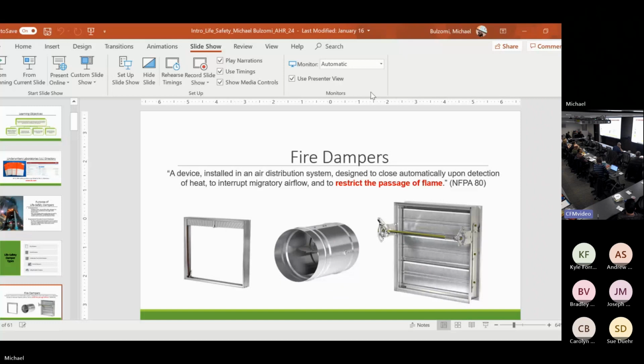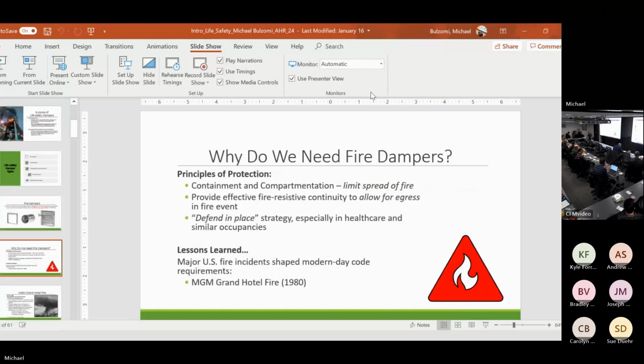I'll show you a couple dampers. Got your curtain fire damper on the left, true round in the center, and then a multi-blade fire damper. It looks very similar to a control damper. It's got a jack shaft, but it's got a fusible link and a helical spring. This spring, the link melts, that spring uncoils, spins that jack shaft, and the blade slams closed.